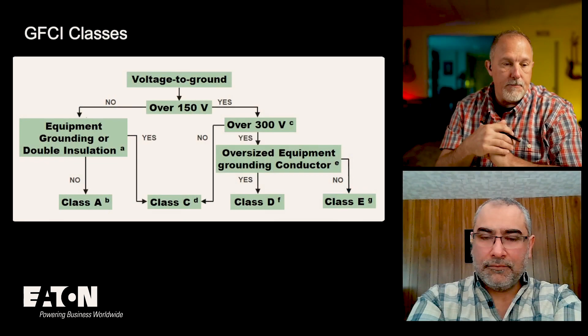Now let's talk about this table, which I believe came from the standard. Yes, it came from UL 943C, the special purpose GFCI UL standard, or more accurately, an outline of investigation, since it's not technically a standard.